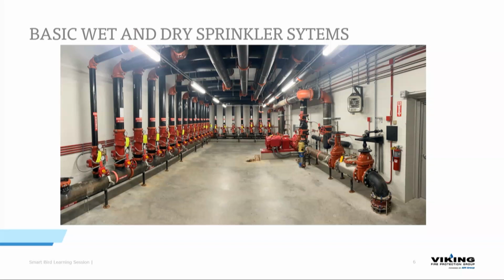Jockey pump just maintains the pressure in the system if there's any fluctuation. We have a bypass loop that goes around the fire pump. So if you ever need to take the fire pump out of service, you have a loop that goes around it so that we can do those services on there and still have at least some water to the system. Test headers back here. I'll show you some pictures of that later and what we do with the test header.